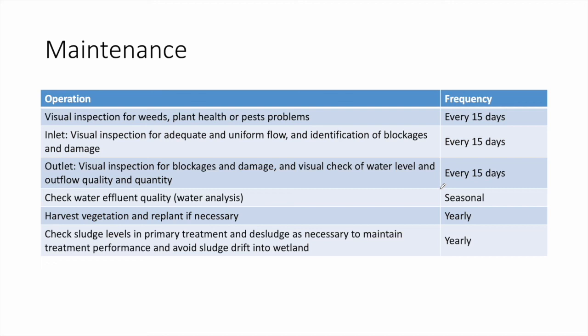Maintenance of a wetland is simple, mainly gardening and inspection. Every 15 days to one month: inspect for weeds and remove them, check plant health and pest problems, and inspect the inlet and outlet pipes for uniform flow, blockages, and damage. Yearly tasks include checking effluent water quality via lab analysis, harvesting and replanting reeds if necessary, and checking sludge levels in the primary treatment tank to maintain performance and avoid excessive drift into the wetland.